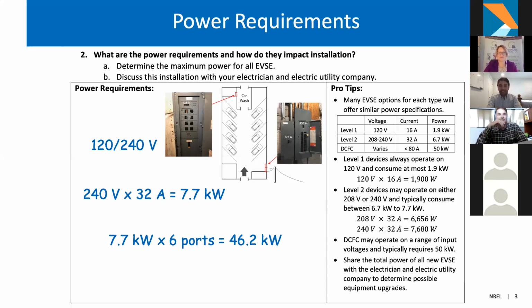So if you are going to upgrade your service panel, one of the best metrics to share with the utility company—obviously the electrician will share the new breaker panel, but you might want to share with them this metric, the 46.2 kilowatts, or just talk about how that load is increasing and why it has the potential to exceed their current capabilities.